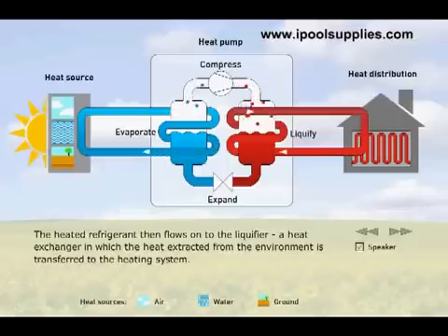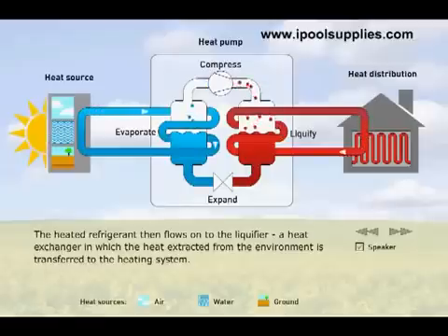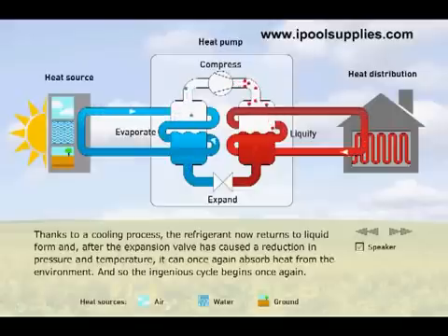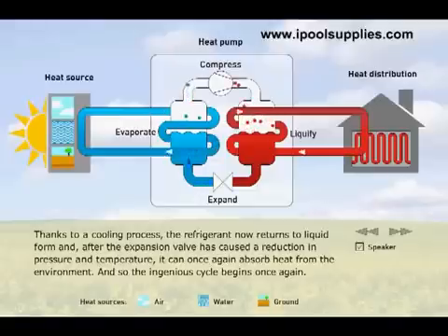The heated refrigerant then flows on to the liquifier, a heat exchanger in which the heat extracted from the environment is transferred to the heating system. Thanks to a cooling process, the refrigerant now returns to liquid form and, after the expansion valve has caused a reduction in pressure and temperature, it can once again absorb heat from the environment. And so, the ingenious cycle begins once again.